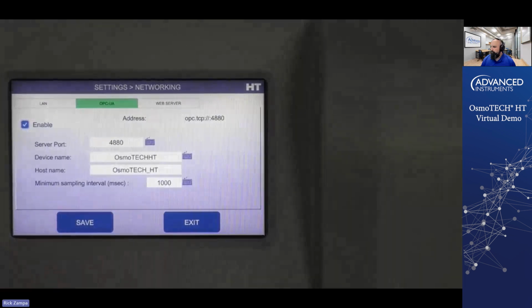You also have OPC-UA, and OPC-UA is a machine language, for lack of a better word, that allows for true bidirectional communication with the instrument. What this would allow you to do is communicate directly to the instrument, load your templates into the system remotely, start testing remotely, get your data, and manage the system remotely through a different system.